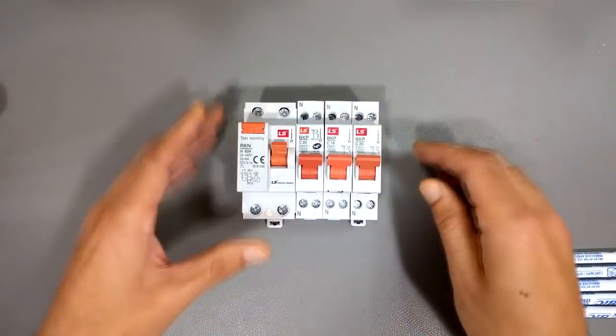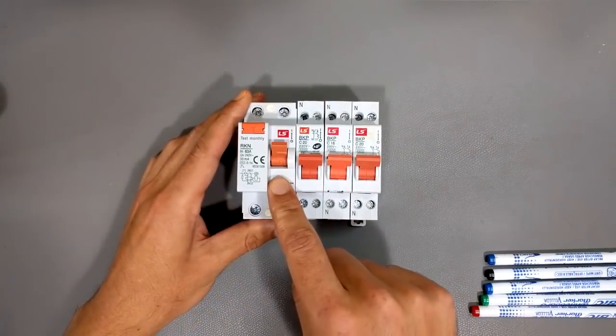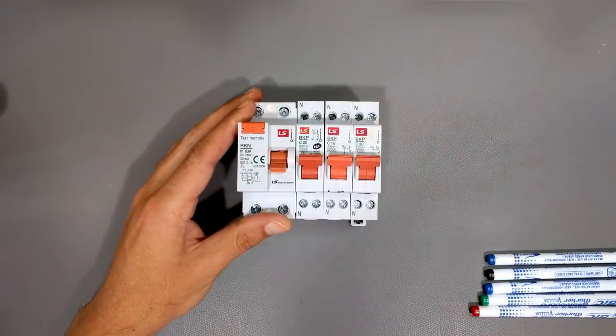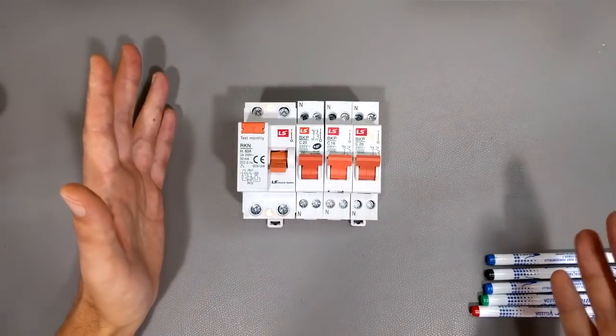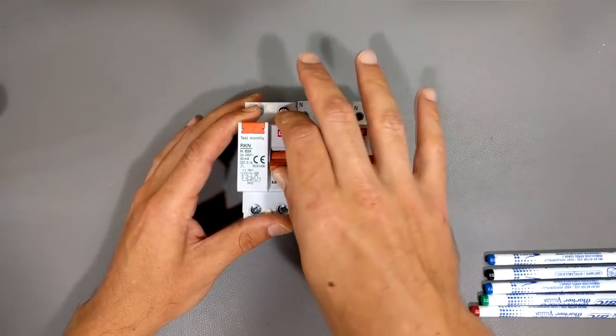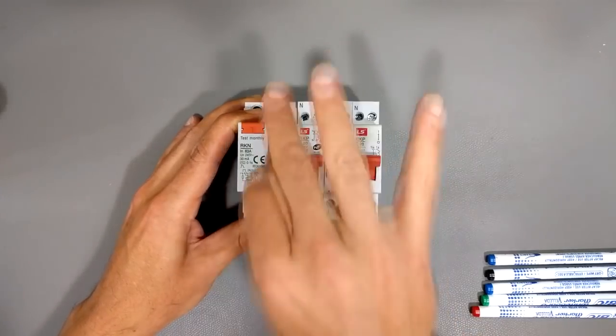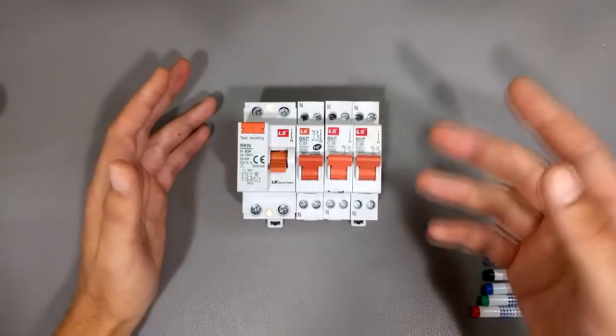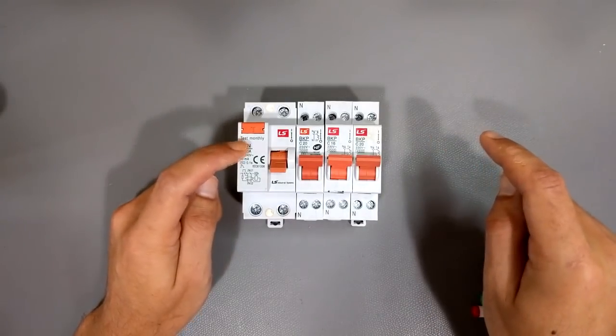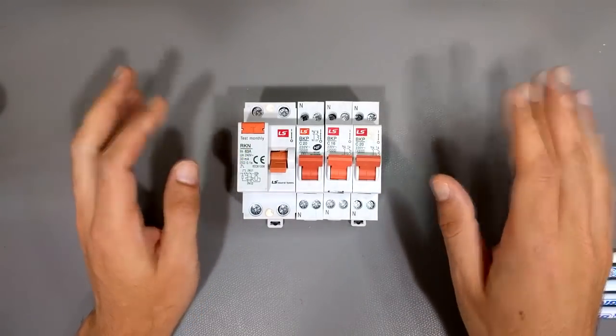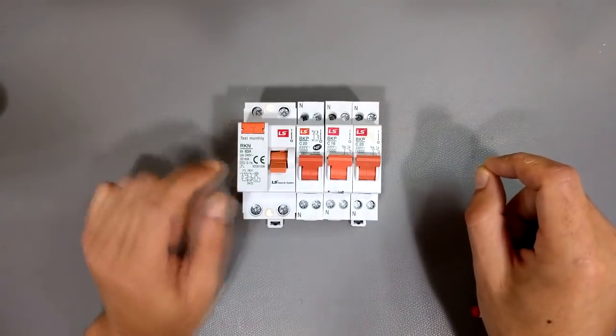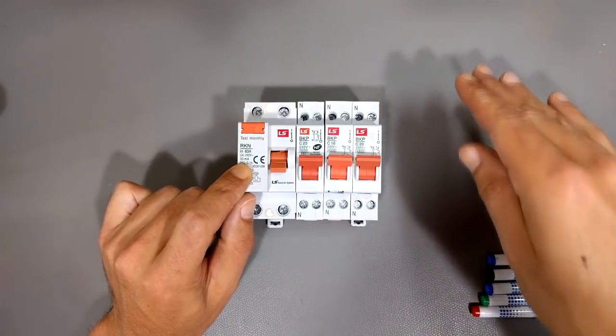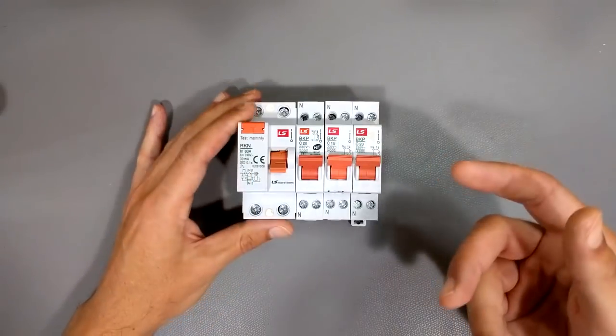Okay, so the first thing and most likely thing that will happen is that the differential breaker slash GFCI slash RCD will trip. Okay, what do you do? Well, normally, like I said, what you do is you go, I'll just turn it back on, and you turn it back on, and it instantly trips. At that point, you want to stop turning it on and off, because the more these things trip, the quicker they tend to wear out, and they become slightly more and more sensitive, so that instead of tripping at 30 mils, they start tripping at like 28 and 27, 26. Essentially, they become more sensitive.